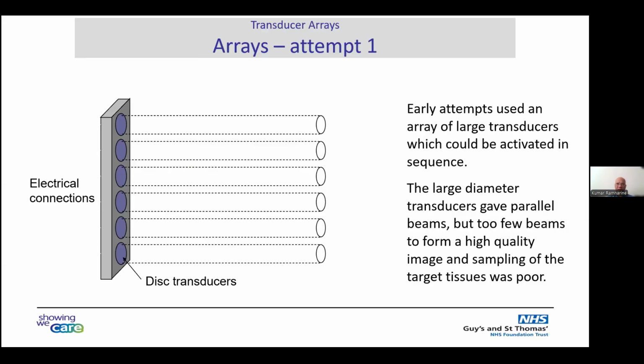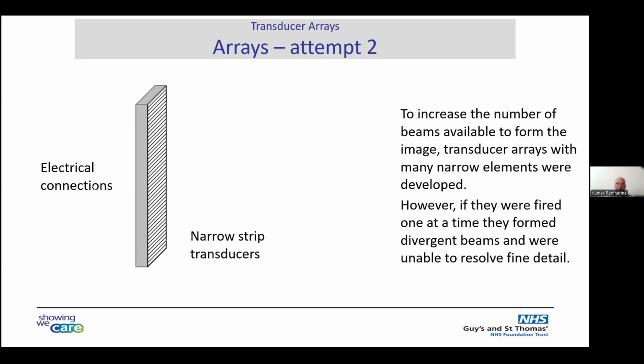The problem with such an attempt is you have these large transducers which could be activated in sequence to produce your B mode image, but the resolution is going to be poor because there are too few beams. The beams are large, so the resolution and the sampling of the tissue is going to be poor. A second attempt you could conceive is if you have many narrow transducer piezoelectric elements. If you just excite one element, then you're going to get divergent beams because of diffraction. If the element is very small, then the beam that's emitted out is a spherical beam, a circular wavefront, which is going to give you a poor image.